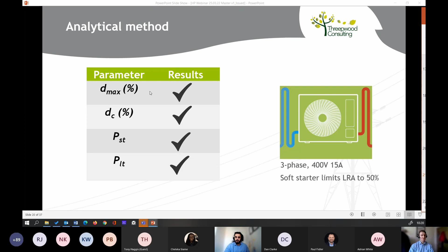Yeah, so as Chelika mentioned, impedance is important - that's what DNOs use when they do their calculations, it's all about impedance. As an example, if we take a 32 amp device connected to a single phase supply, that gives you an impedance requirement of 0.218 ohms with a short circuit power level of 243 kVA. You can see on the diagram you've got your mains cable, your LV service cable, and your fuse which goes into your house. So that's 0.218 ohms at the PCC, which is just at the bottom there.